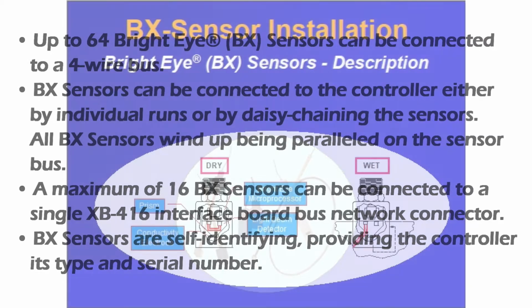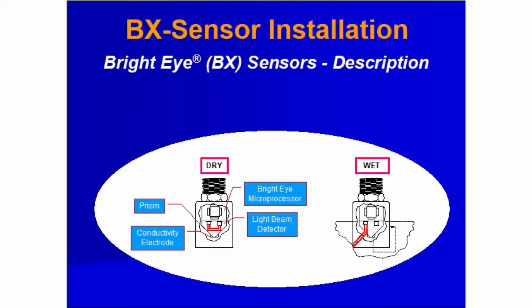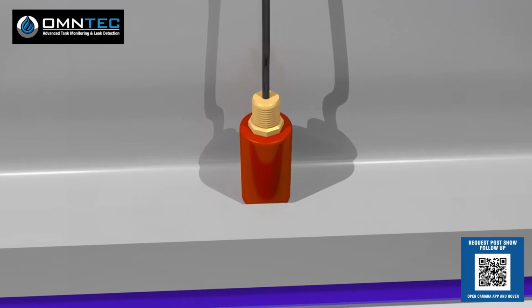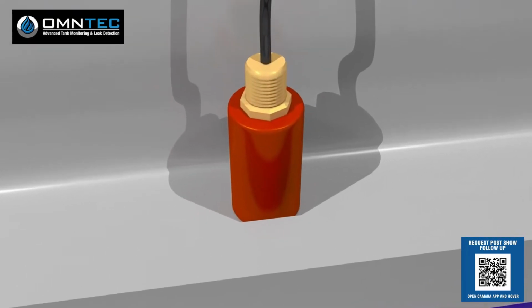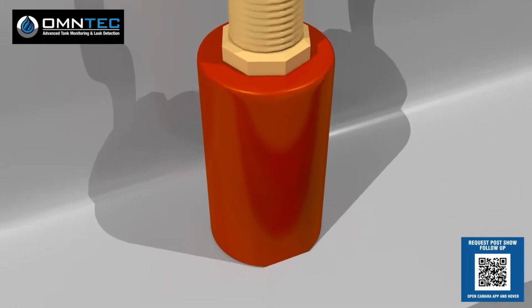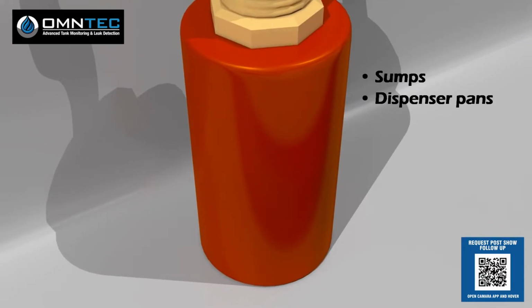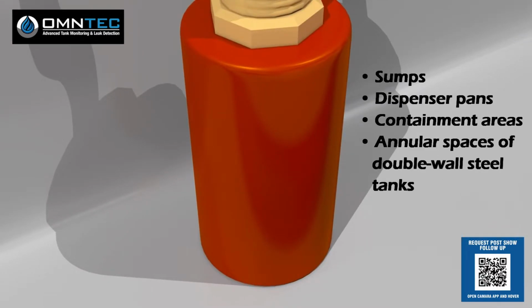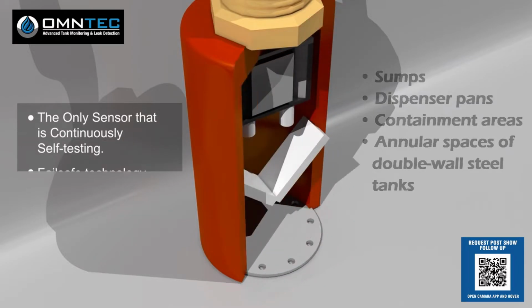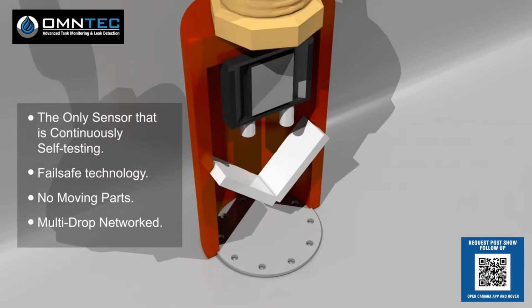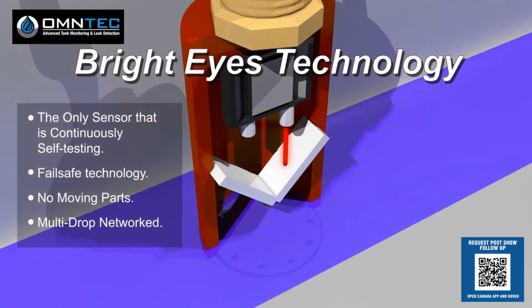BX sensors are self-identifying, providing the controller its type and serial number. BX optical sensors operate on the principle of light refraction, and with their convenient size and ability to detect liquids at any angle, these sensors are ideal for sumps, dispenser pans, containment areas, and the annular spaces of a double-wall steel tank. Under a dry condition, light from an LED bounces through a prism and is seen by an LED detector. The signal produced by the microprocessor sends a normal condition to the controller.